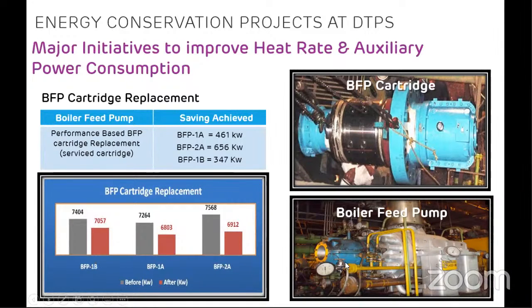So any small amount of power saving in this auxiliary will be a huge saving for the auxiliary power consumption of the plant. When we replace this cartridge, it reduces all the losses inside the pump, which are due to internal leakages and recirculation. So these losses are eliminated, and by replacing the cartridge, we get lower power consumption. For BFP 1A, we achieved a saving of 460 kilowatts. For BFP 2A, we achieved a saving of 650 kilowatt. Likewise, it varies with the cartridge replacement, and you can see from the graphs that from 7,404 kilowatt, we reduced it to 7,057 kilowatt, and likewise for the other boiler feed pumps.